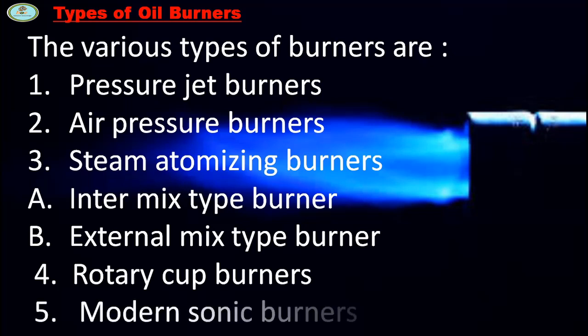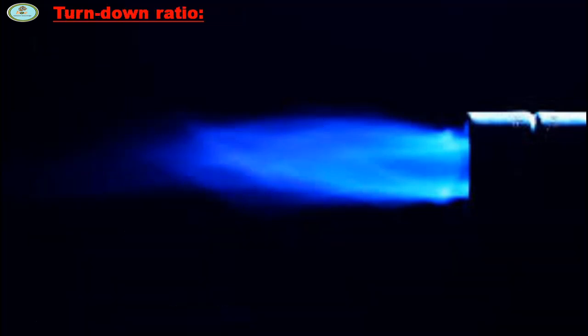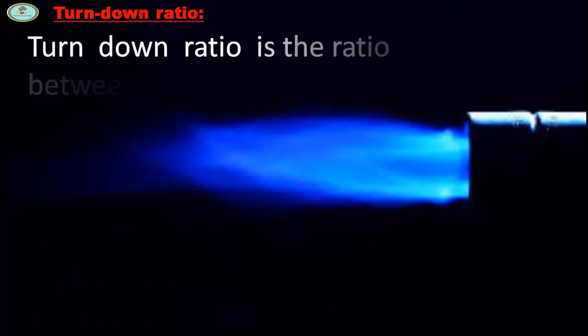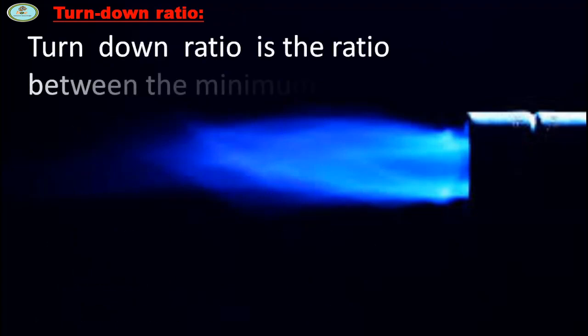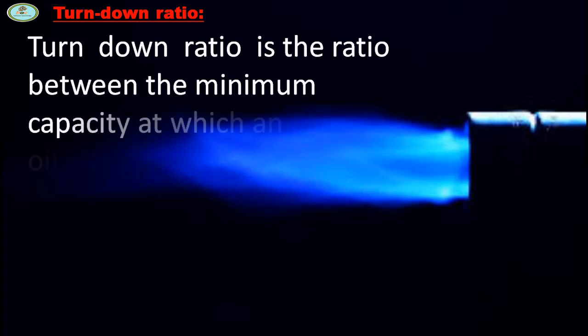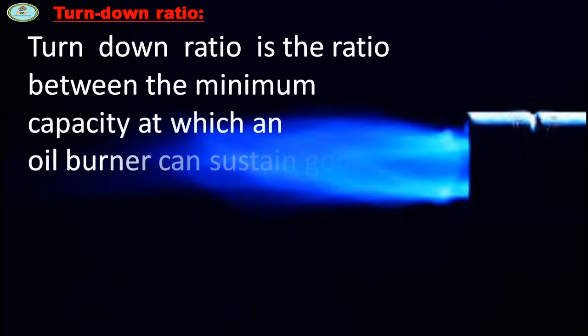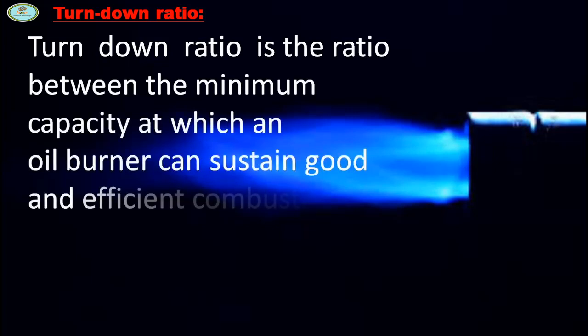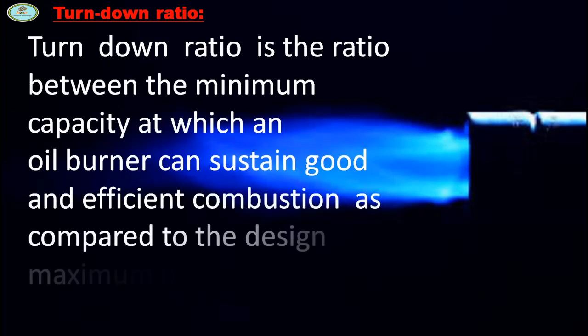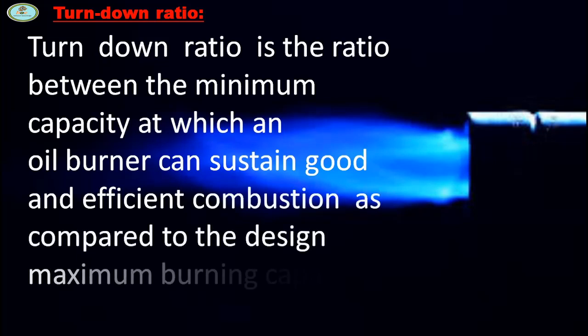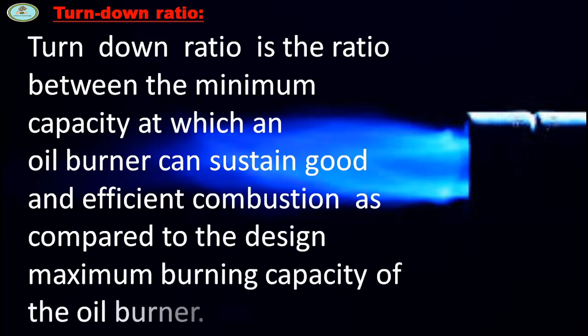Turn down ratio is the ratio between the minimum capacity at which an oil burner can sustain good and efficient combustion, as compared to the design maximum burning capacity of the oil burner.